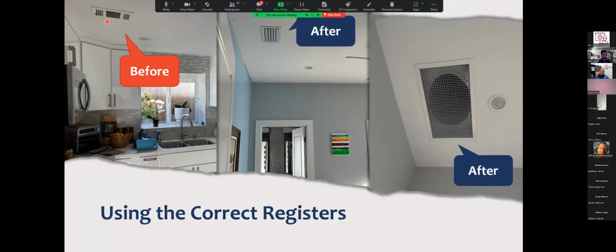And spread registers work pretty good if I have an oversized system that's going to have a very short cycle, because basically it throws a little air over here, a little over here, and a little over here. And so it gets a little bit of mixture on very short cycles. So those registers are okay with an oversized system. But when we put in a heat pump that we intentionally know is going to run longer cycles, we're using these single direction curved blade registers.